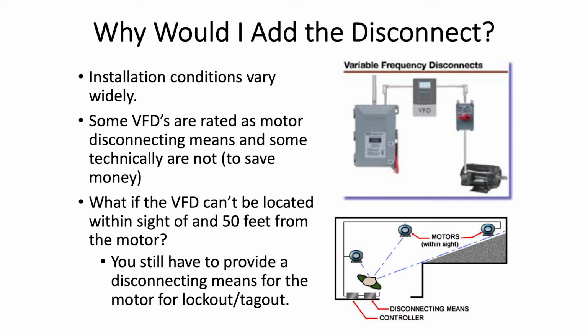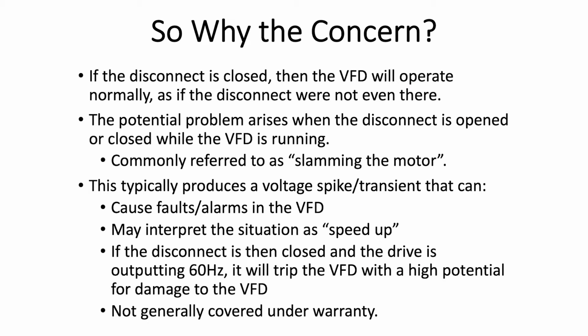So why would I want to add one? There's your slide. Some VFDs are rated as motor disconnecting means. Some technically are not. So if my VFD is not rated as a motor disconnecting means, the inspector says, I don't see any rating as a motor disconnecting means on that brand of VFD, you need a disconnect. Okay, now I need one. What if the VFD can't be located within 50 feet or sight? Now I need one. So those are reasons.